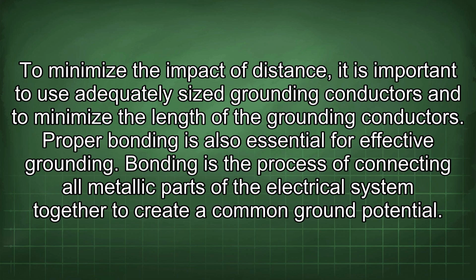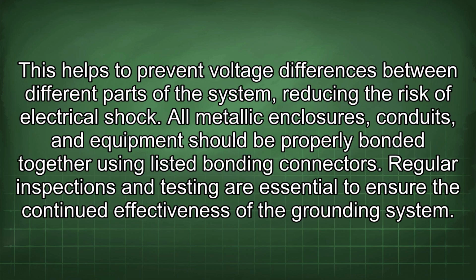Proper bonding is also essential for effective grounding. Bonding is the process of connecting all metallic parts of the electrical system together to create a common ground potential. This helps to prevent voltage differences between different parts of the system, reducing the risk of electrical shock. All metallic enclosures, conduits, and equipment should be properly bonded together using listed bonding connectors.